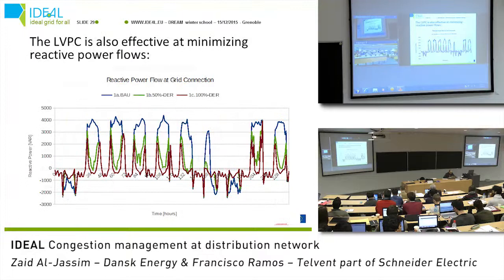The low voltage power controller is also effective at minimizing reactive power flow. Here we show a baseline, which is the blue line, the reactive power flow in the network measured near the transformer, and the green line shows the minimized reactive power achieved by the low voltage power controller.